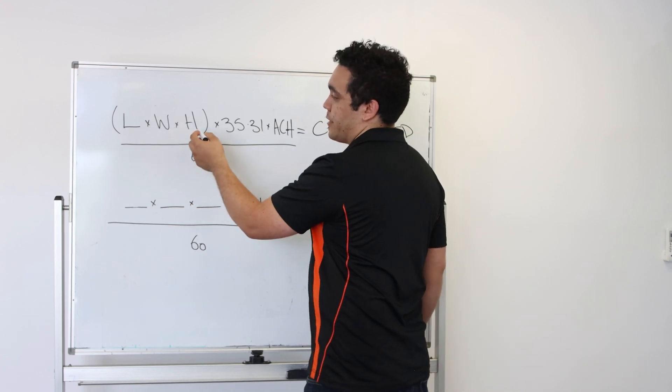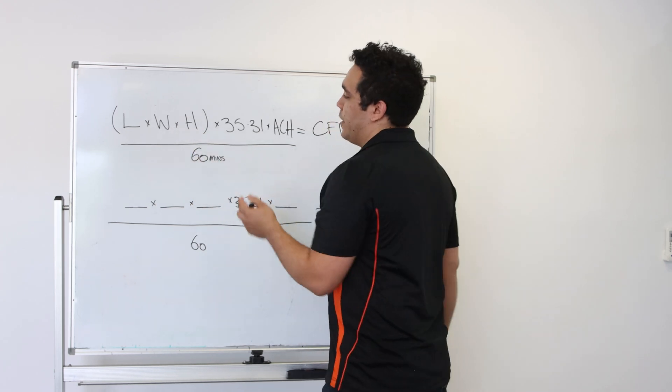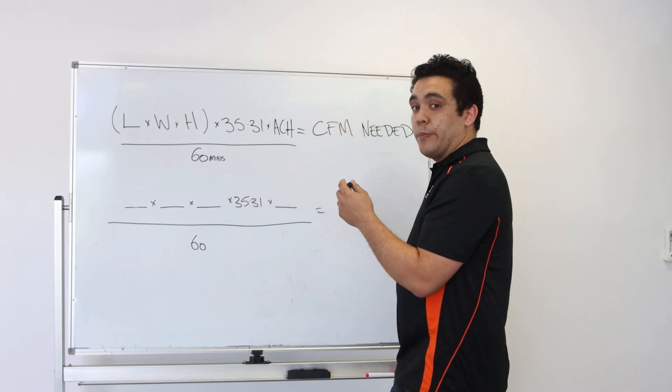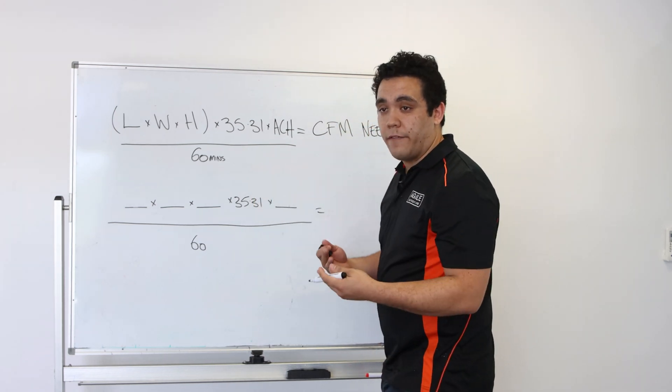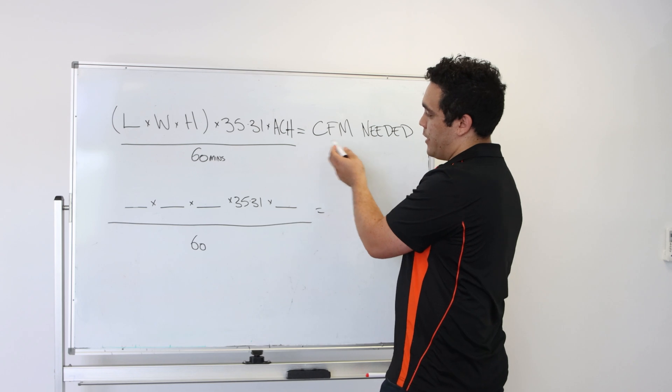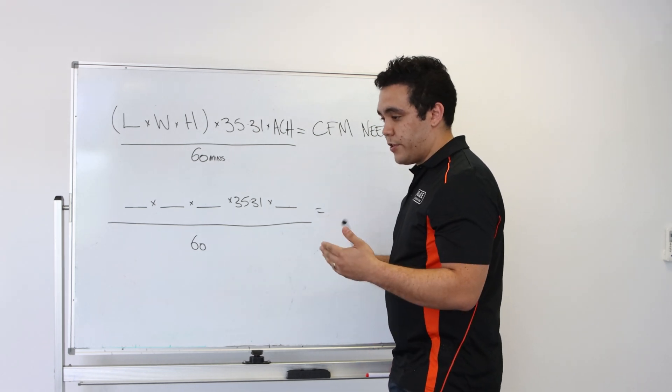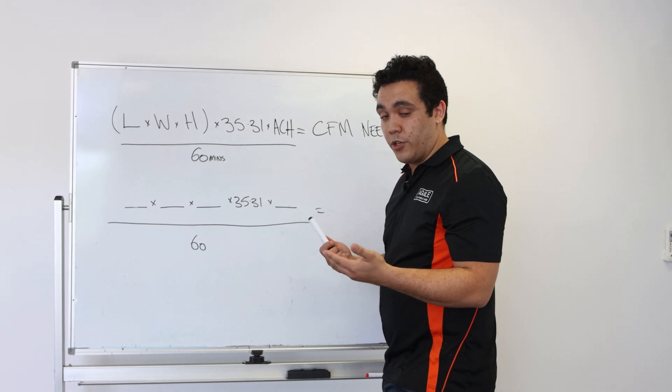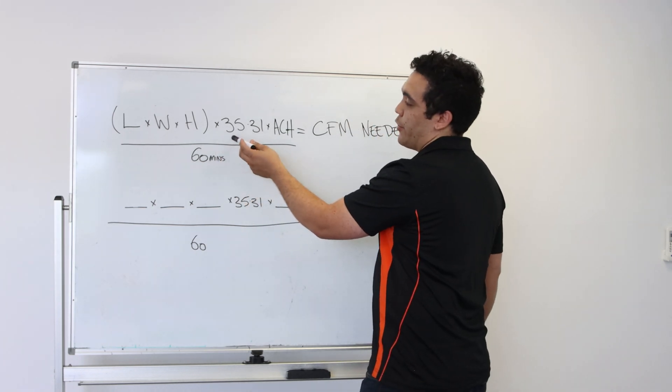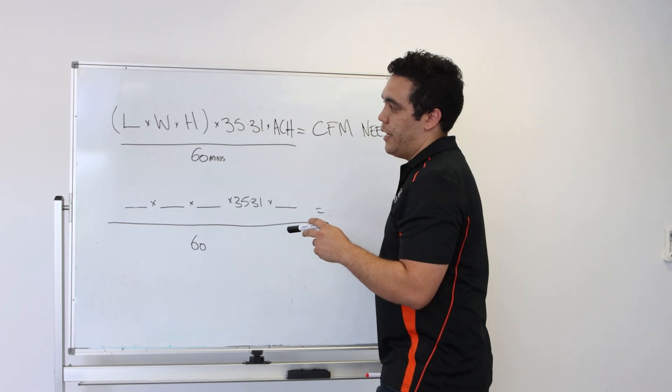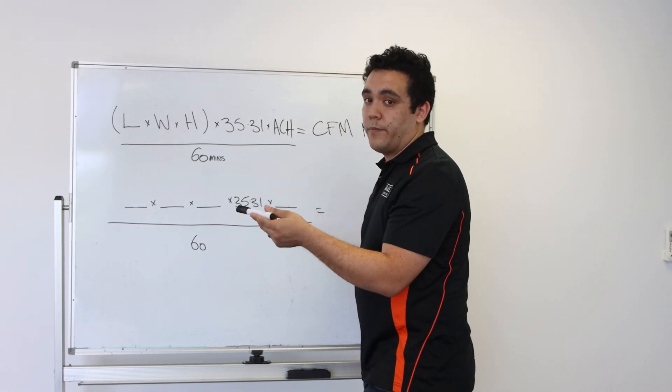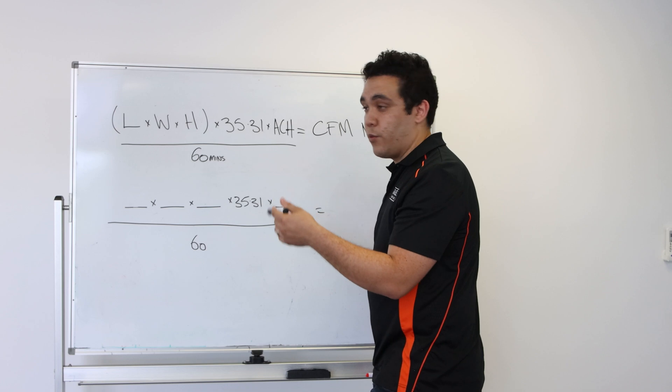So that's the length times width times height in meters, and because most air filter units are described in CFM, it means we'll need to convert to imperial units to cubic feet. So we multiply that by 35.31, and that'll give us the amount of cubic feet of air in the room.